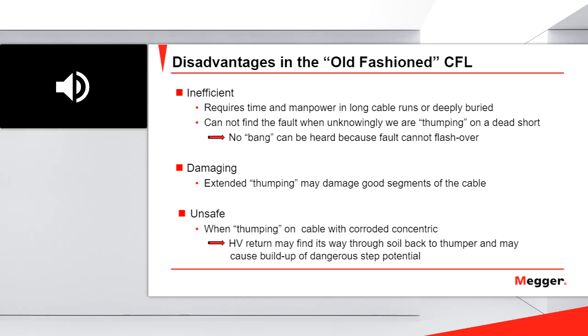But the worst scenario is when we have a fault, and this fault is a short. Let's say that the fault I'm trying to find is a short between the conductor and the concentric. So if I send a high voltage pulse through the cable, there will not be a bang. There will not be noise when the pulse arrives at the fault. Why? Because we have a short, so there is no flashover. There is no arc. So in this case, the worst is that I will just see my thumper charge and discharge the high voltage pulse, okay? And I will assume that at some point in my cable I need to hear the arc, the bang of the fault, but I don't know that I have a short. And for that reason, I will spend a lot of time trying to hear a bang that doesn't exist, okay? So this is the worst scenario in this case.